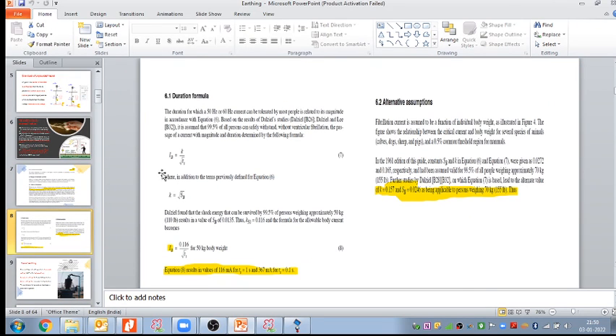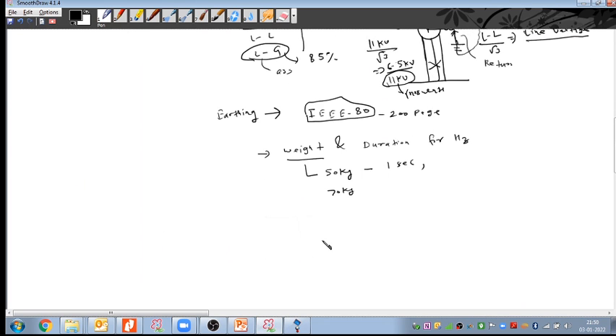Here is the statement we can deliver: a 50 kg person for a 1 second duration can tolerate 116 milliampere. A 70 kg person for 1 second can tolerate 157 milliampere. Now you have the reference standard for this, what the reference standard is. And now you have the formula also.